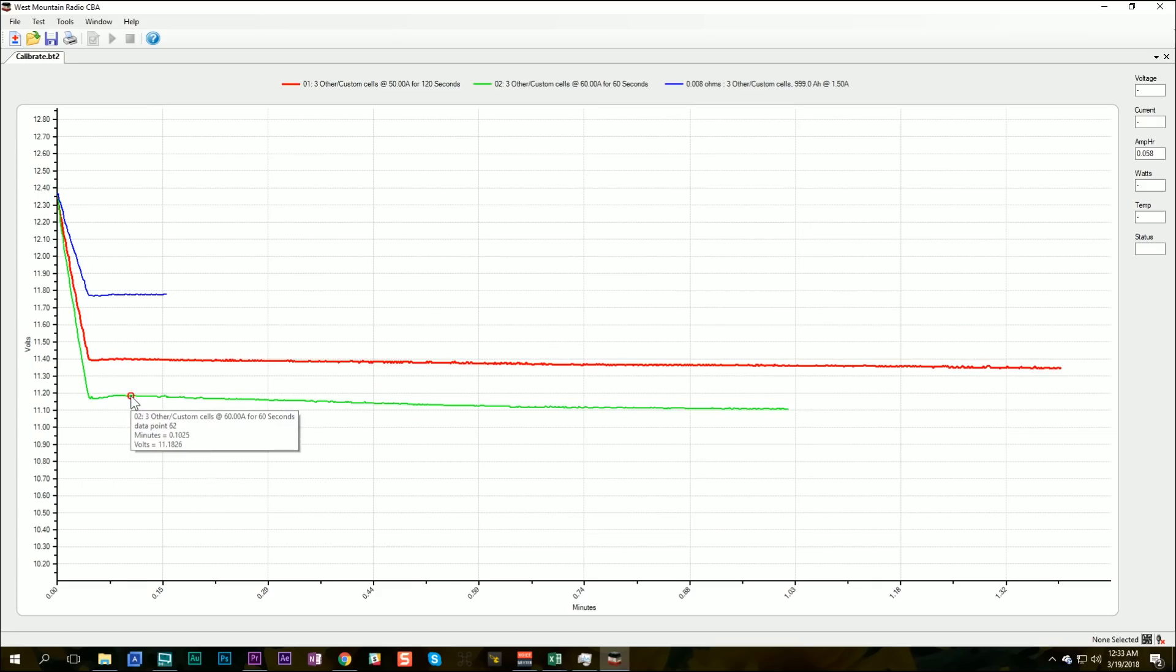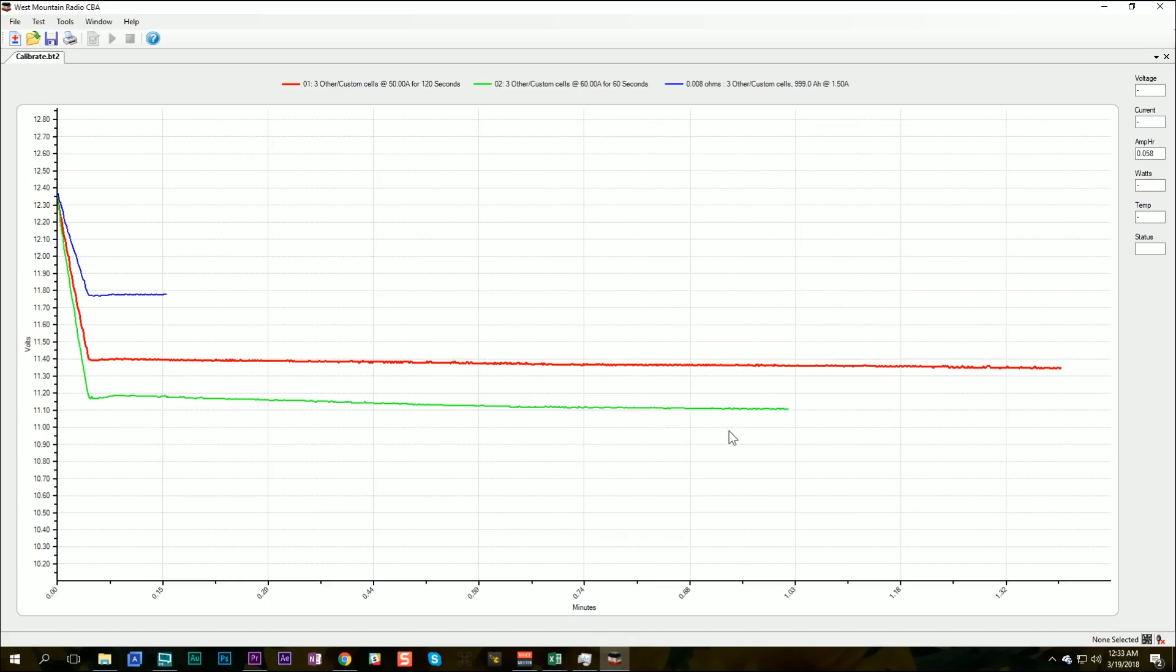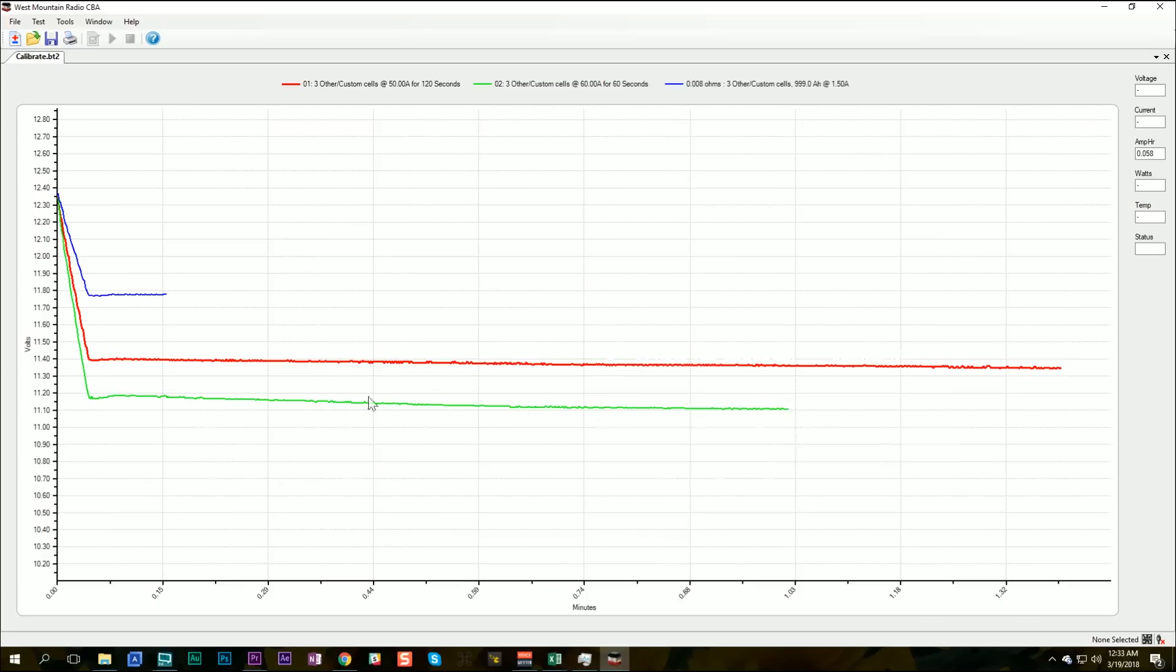This test shows 60 amps for one minute. We start the test at about 11.18 volts, and by the end of the test, we're down to 11.10 volts, so 80 millivolts.